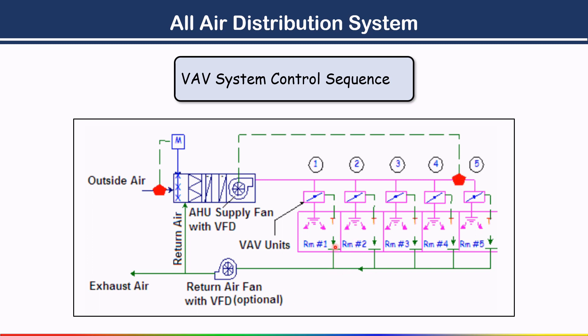Return air from the rooms is returned to the AHU; some air is exhausted to the atmosphere and fresh outside air is introduced to make up the balance. The supply fan is speed-controlled by a variable frequency drive and delivers air to individual rooms. The system serves multi-zone air conditioning with a VAV terminal box for each zone or room.